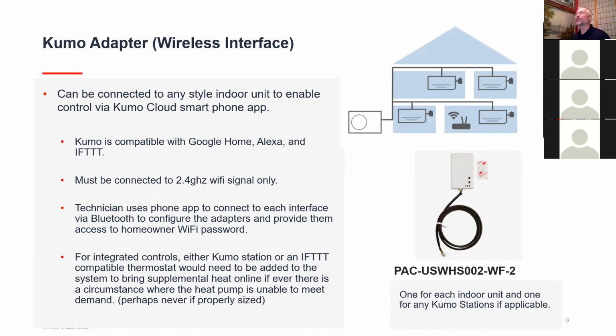Okay, so with that being said, the basis of any of the Kumo options, whether you're talking about IFTTT or using a Kumo station, one of the core things that would need to be incorporated into the system is a Kumo adapter for each one of the indoor units. Okay, and the Kumo adapter, it's like a large pack of gum size adapter and a 3-foot or so cord dongle that plugs into the CN105 port of any of our indoor units.